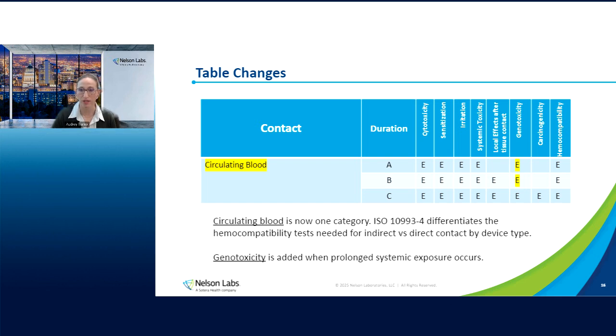However, this applies for extracorporeal circuits. So this is where blood is being pulled from the patient and then manipulated and then pushed back to the patient, so that even if the exposure was short-term inside the device, if the blood has pulled something from that and put that then back into the patient, where it will circulate through the patient's body and could cause a genotoxic effect before it is removed from the patient.